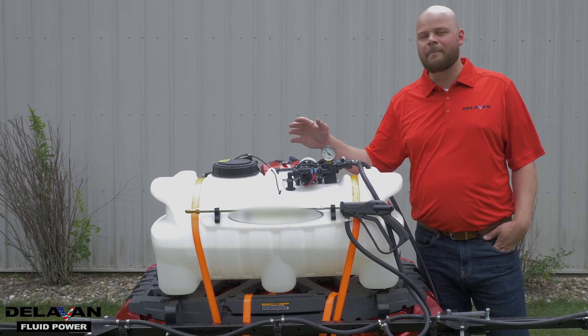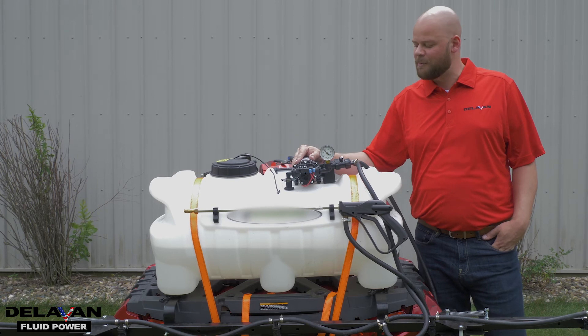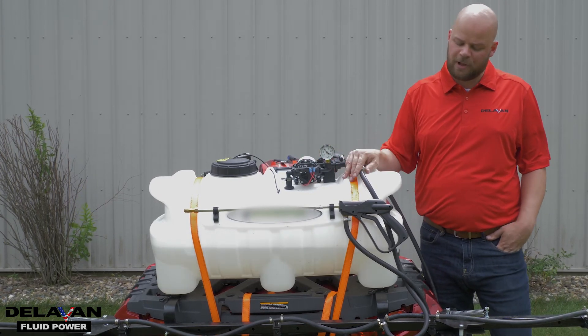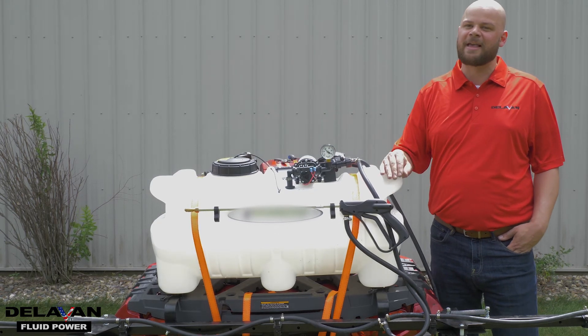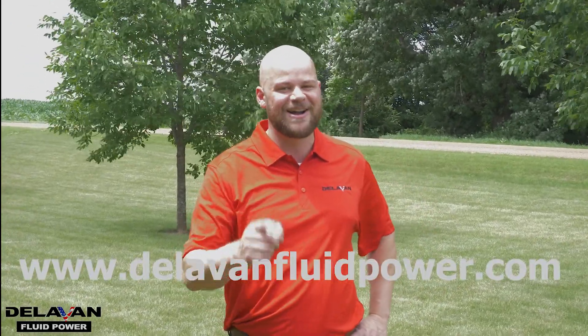So that was our video on how to combat cycling on your Delavan Fluid Power pump. One thing to know about cycling is that it means too much flow is going to your sprayer system than it can handle, so you want to open up your bypass to combat that cycle. For more information, including FAQs and videos, visit our website at www.delavanfluidpower.com.